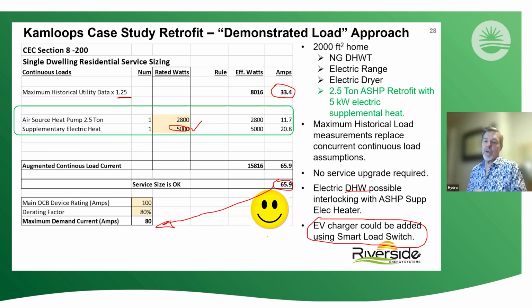Yeah, as you pointed out earlier, a service size upgrade is always an inconvenience, and costly. So if there's a way that you can avoid doing that, like putting in a smart panel that maybe is as expensive as a service upgrade, or maybe is half of it, the point is that it gives you much greater flexibility with your new system than if you stayed with an old system but larger. Well, doing a service upgrade is going to trigger a panel upgrade regardless. Then that is the opportunity to put in a smart panel. But if you can, by all means, avoid doing a service upgrade.